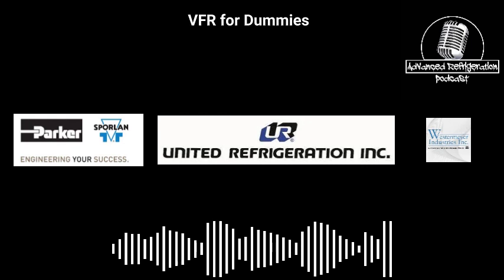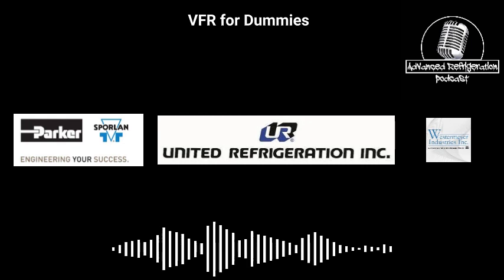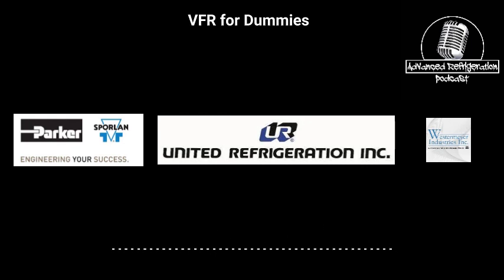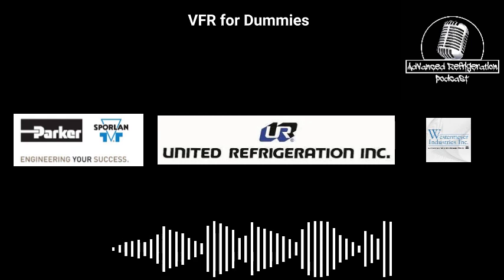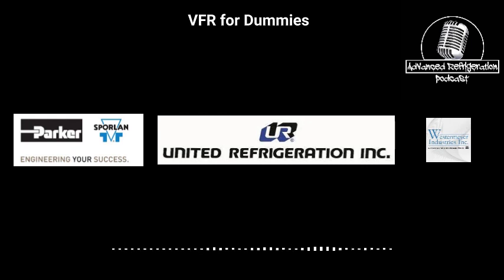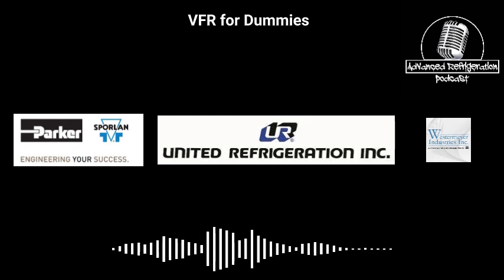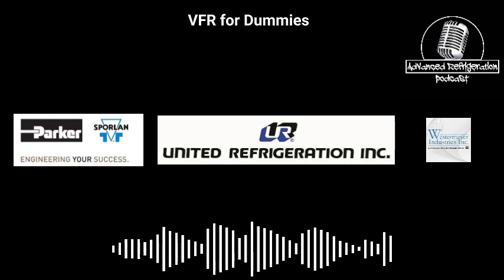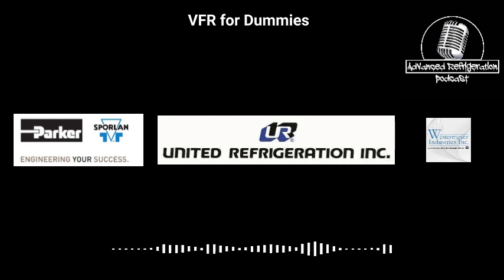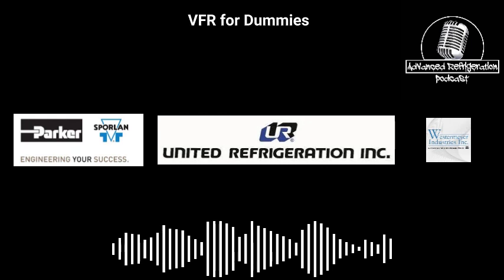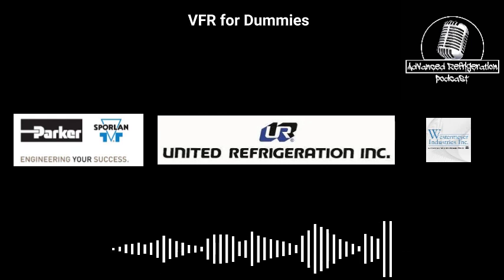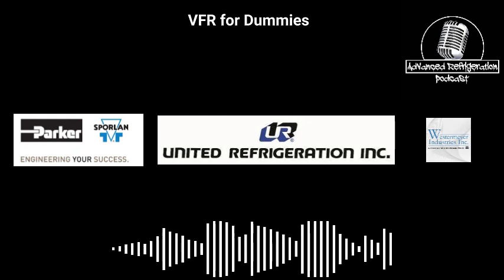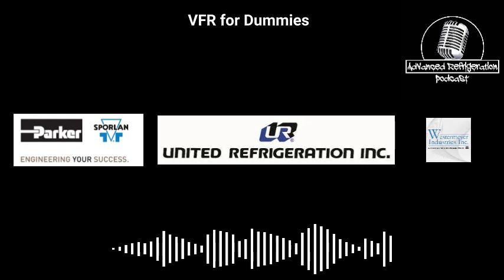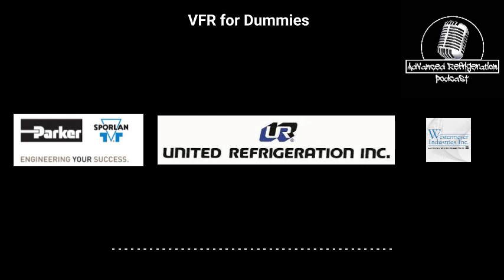If it's short on gas, you're going to start seeing discharge superheat climbing. We have a broad range, well, at least Daikin does, of like 27 to 82 degrees of discharge superheat. So as long as it's within that range, we can say it's probably okay. As soon as we start approaching 80, 85, 90, we're probably looking at a low refrigerant charge situation. So they're dependent on, go ahead.